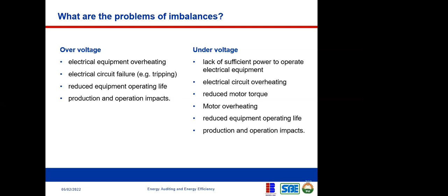If it's under voltage, it can cause similar problems, like lack of sufficient power. If there's under voltage in your system, you have insufficient power to operate your electrical equipment. That's why when some people say they have low current, it's not necessarily low current - what they actually have is low voltage. The low voltage isn't pushing enough current to power your electrical systems, so it might not be able to power the equipment. Under voltage can also cause electrical circuit overheating, reduced motor torque, motor overheating, reduced equipment operating life, and production and operation impact.